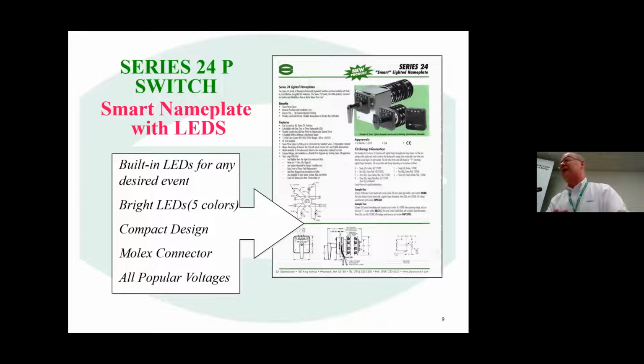So you locally get a mechanical switch composition identification, an LED identification, lighted for on or off, or stop and go, or for up and down, whatever you want to configure it for, as well as the different popular voltages that are used in a switch configuration. In the utility industry, it's 24 volts DC, 48 volts DC, 125 volts DC, and 250 volts DC. Those are the most common voltages in the utility world, but we can also do it at 120 volts AC if you need that kind of configuration.